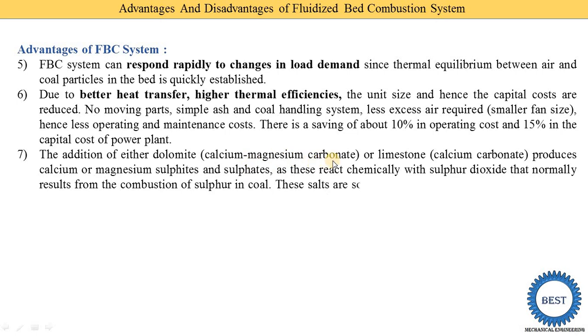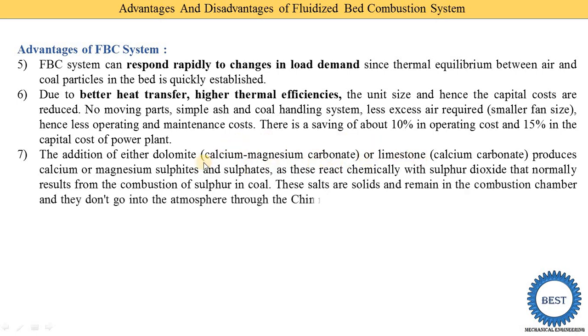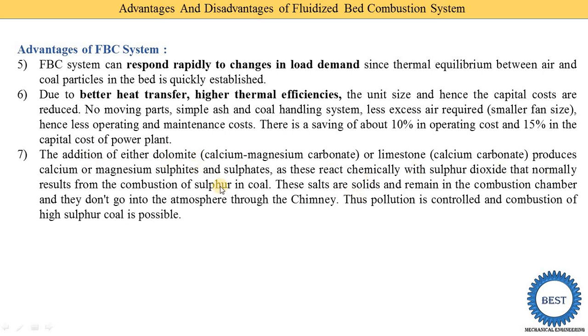The addition of inert materials — either dolomite (calcium magnesium carbonate) or limestone — causes them to react chemically with sulfur dioxide, which normally results from combustion of sulfur in coal. These reactions produce calcium or magnesium sulfate, which are solid salts that remain in the combustion chamber and do not escape to the atmosphere through the chimney. This controls SO₂ pollution and makes combustion of high-sulfur coal possible.